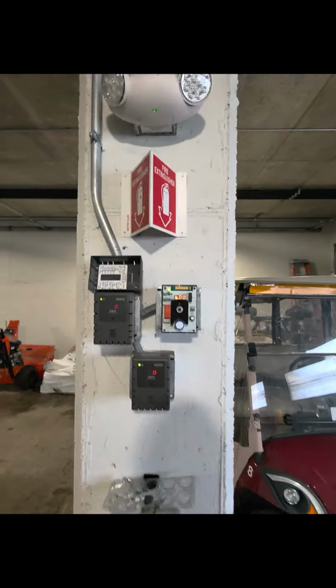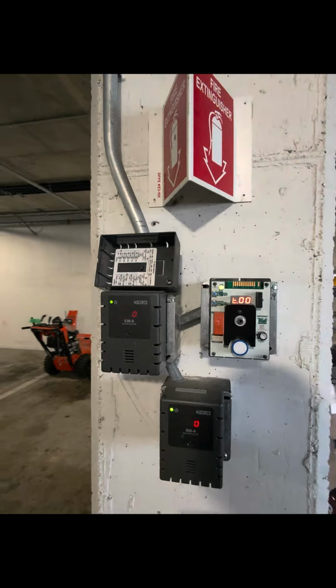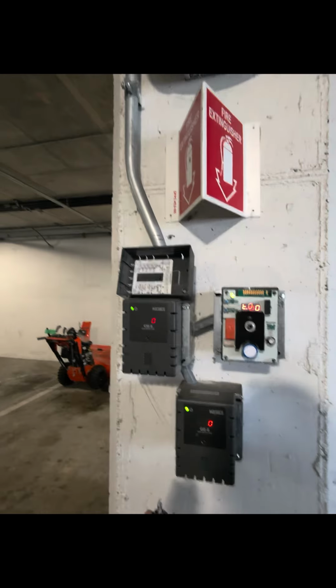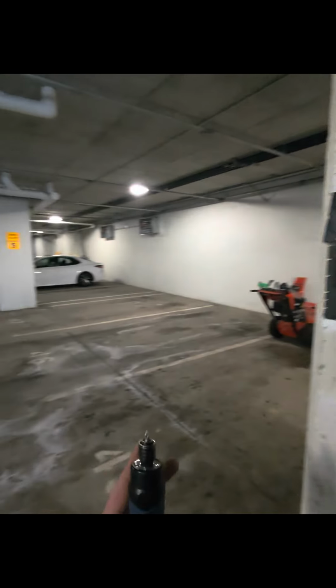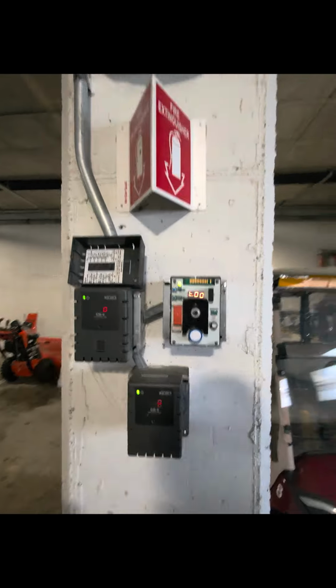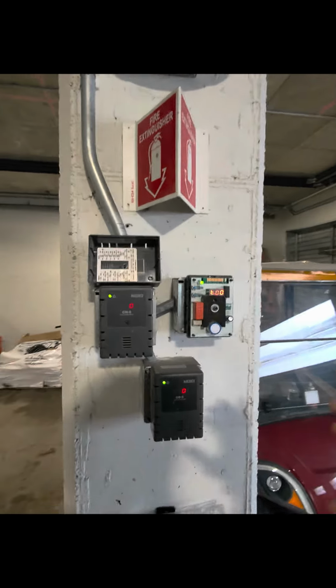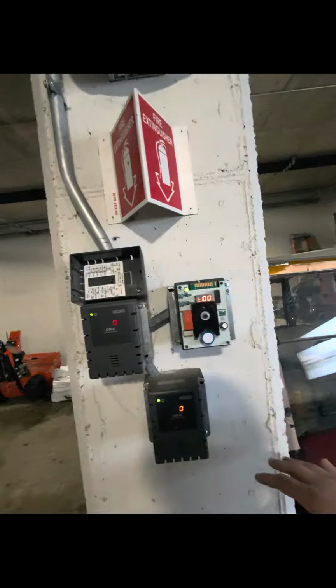We got the T100 trouble, so that's basically just telling you that it's low sensitivity. We want to let this device sit for at least 5 minutes so that it can get the ambient air in here, and basically you want the levels to set. So we have a couple more we have to replace. We're going to go replace those, then we'll come back. I'll show you guys how to calibrate this and test it.